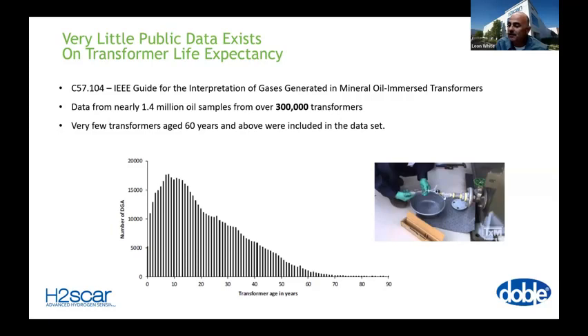But the interesting thing is, if you look at the 300,000 transformers that were in the IEEE data set, you notice that most of the DGA samples are being performed on transformers that are in the 5 to 20 year range. And after the 20-year point, you start seeing a fairly rapid drop in the amount of samples available from transformers that are 20 years and older.